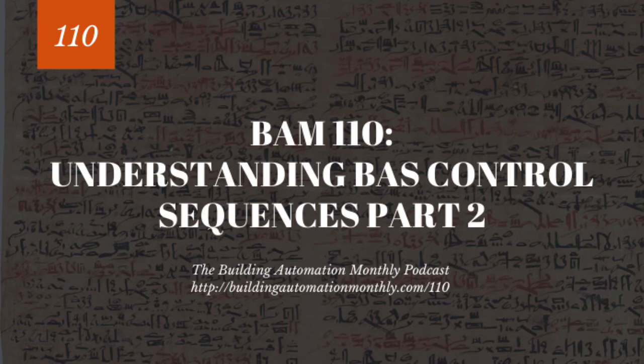Then once you get to that point, what happens is you go to this called heating CFM. So it's slightly higher than minimum airflow. It's typically about 20 to 30% of max airflow, somewhere in that. That's not a hard set rule, but that tends to be where it ends up.